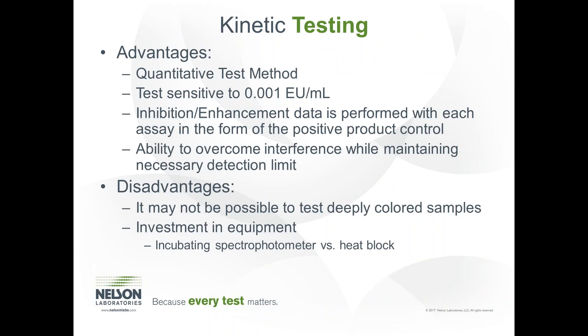There are significant advantages of kinetic testing over the gel clot method. It is a quantitative test with very sensitive assay capability down to 0.001 EUs per ml. Perhaps the biggest advantage is that inhibition enhancement is performed with every assay in the form of a positive product control. Because it is such a sensitive test, if interference is detected, it can usually be overcome with dilution to obtain a valid result. Disadvantages are that deeply colored samples may not be testable with this method, and the investment in a spectrometer and software is significantly more expensive than with the gel clot test.